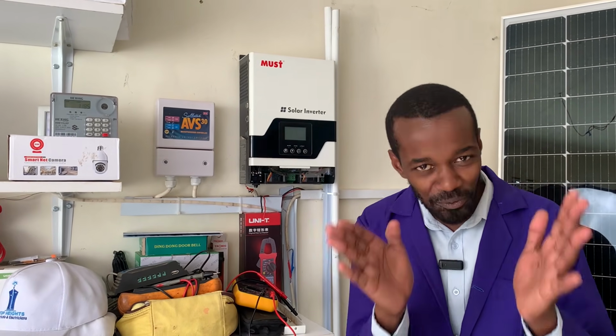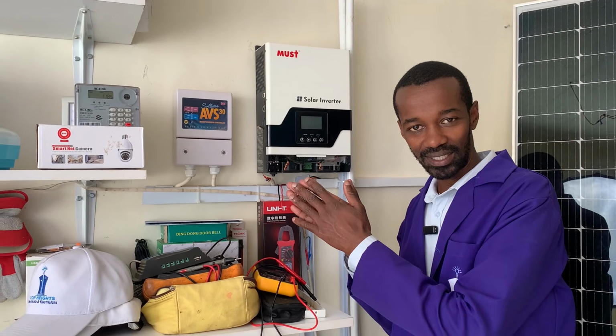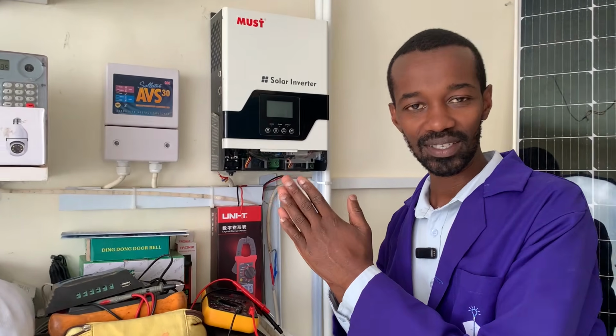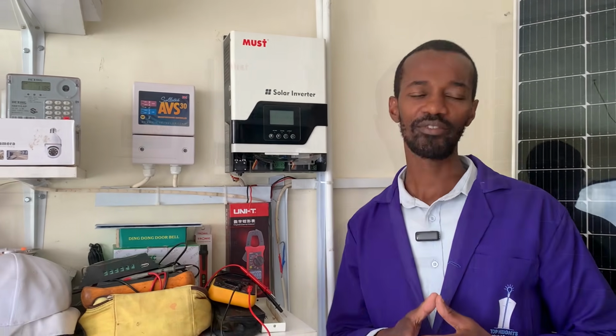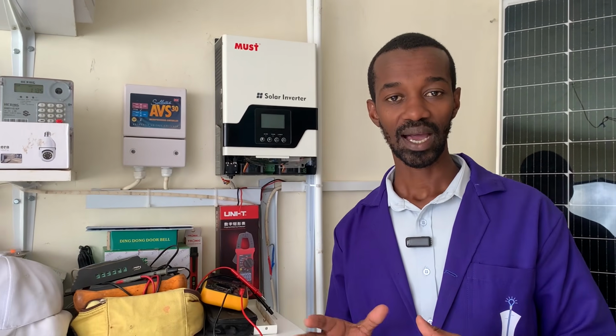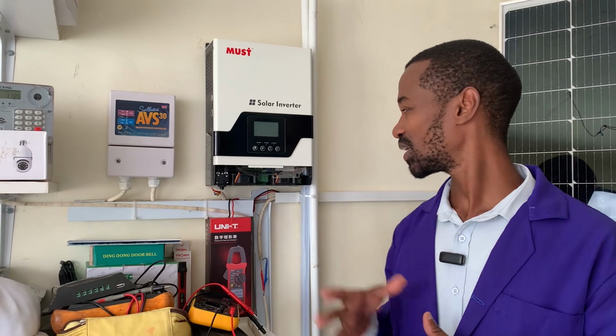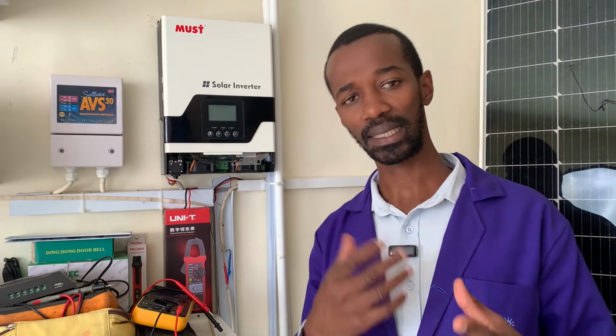My top boss, after disconnecting everything from the inverter - that is the AC incoming, the AC outgoing meaning the loads, and even the battery as well as the panels - the inverter is not connected anywhere. Now we can remove the inverter, assuming that we want to do maintenance work, blow it, or probably do some cleaning works on it. Now, upon connecting it back, there is also a procedure.